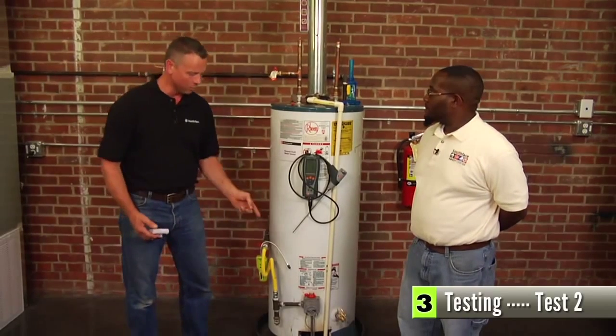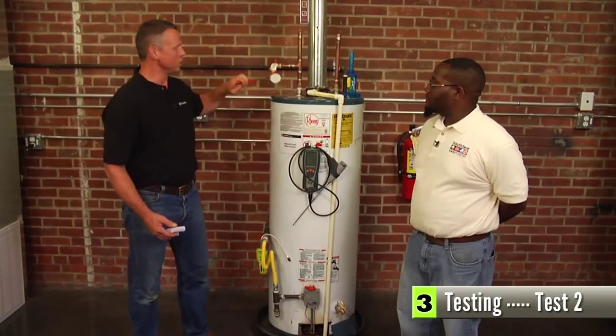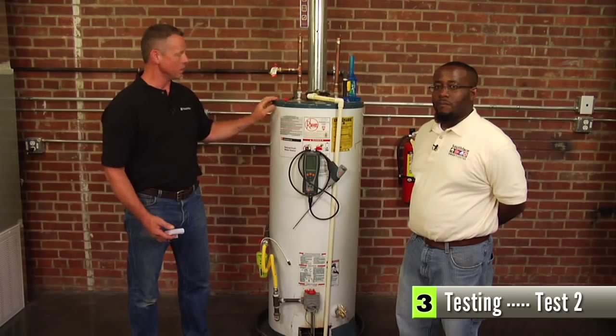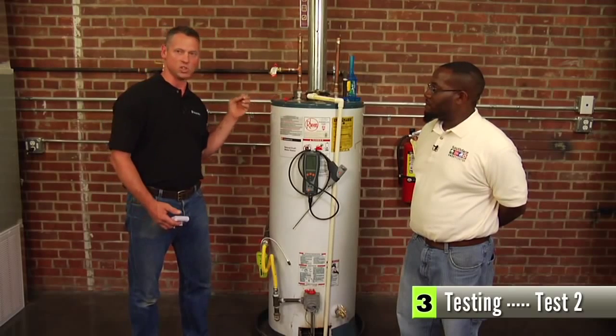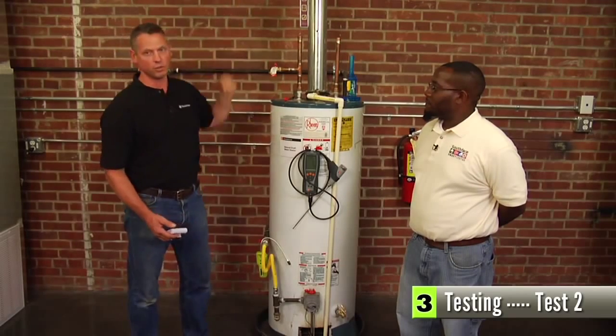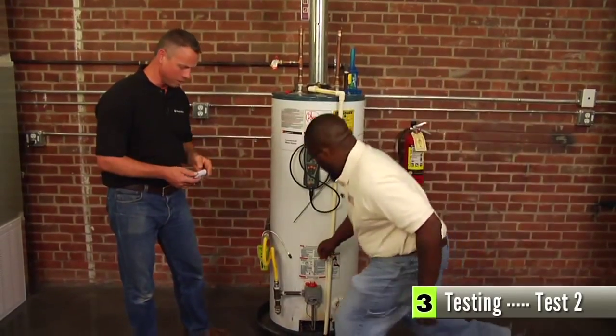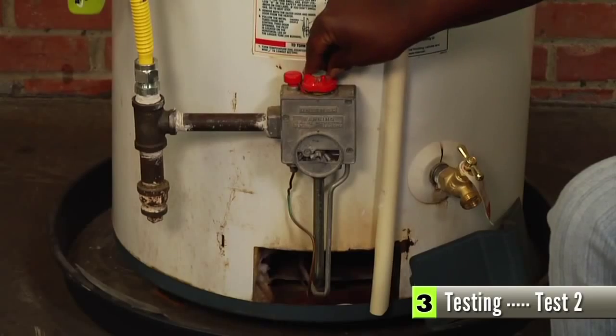So to do that, we turn on the appliance, and then we check for spillage with a mirror. We watch the fog on the mirror, and when the fog goes away, the appliance has stopped spilling, and that means all of the flue gases are escaping up the pipe. So Benson, let's do it. You turn on the appliance, and I'll start the stopwatch.